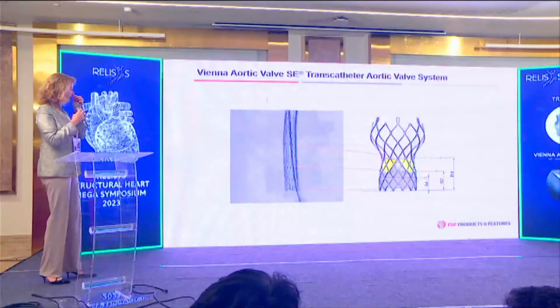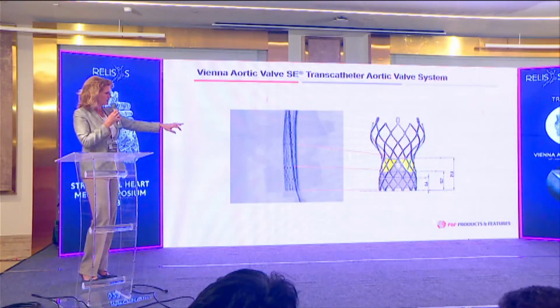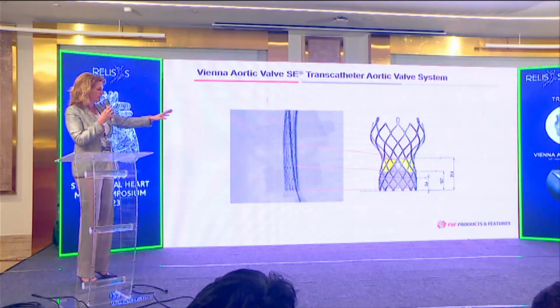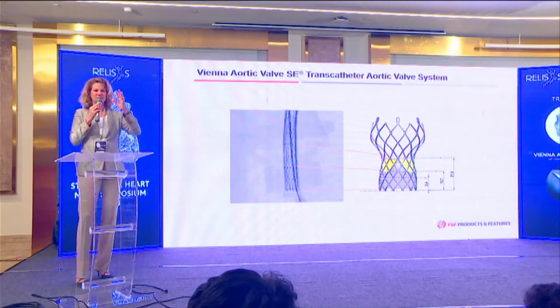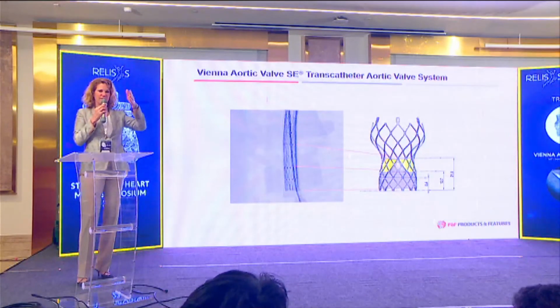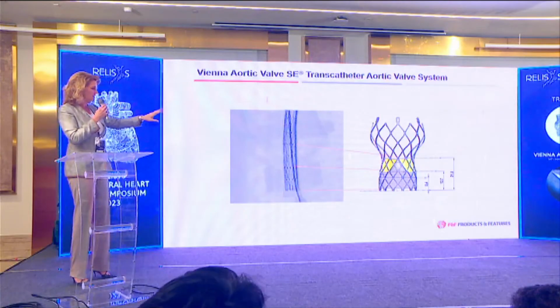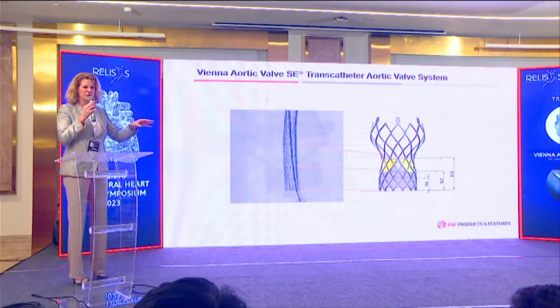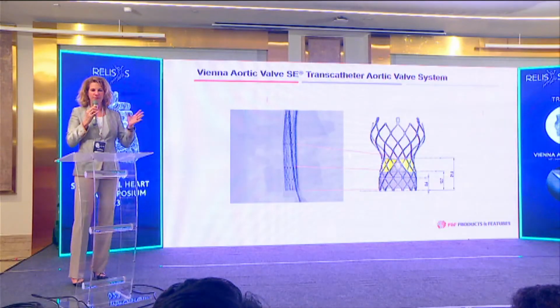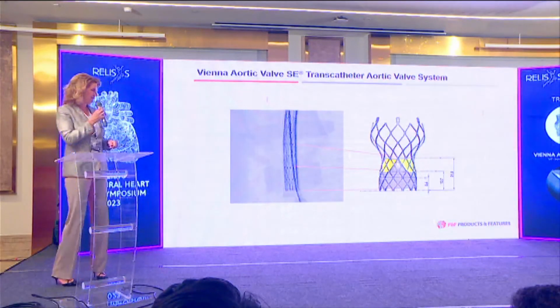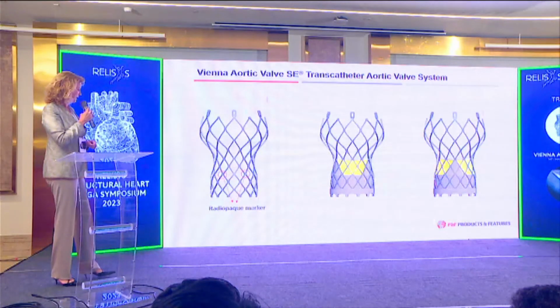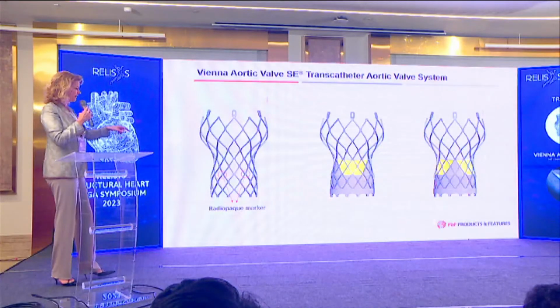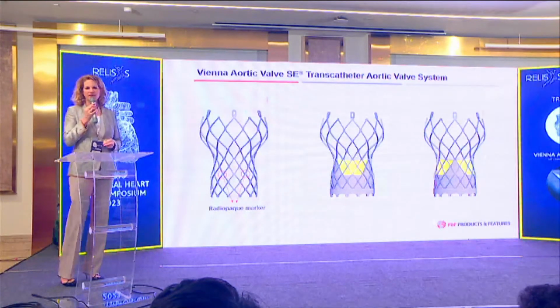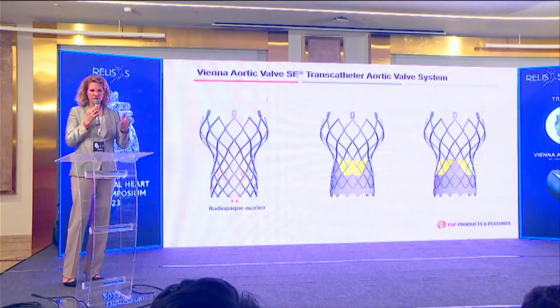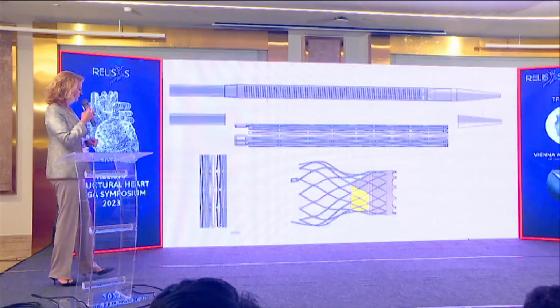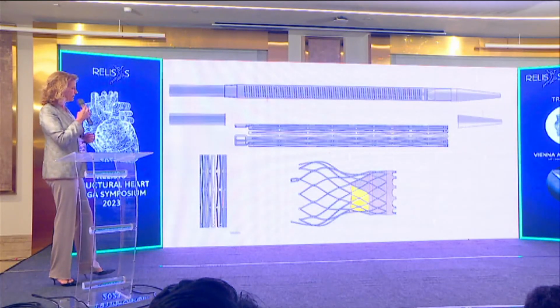Next slide, please. This we have seen, it's a very low skirt with 8.4 millimeters. If you remember the image of the Evolut, you can see that this has a much higher skirt, other leaflet geometry. So this has a low skirt with a very favorable leaflet geometry, which also has a good opening if you look at the leaflet geometry from above. Next. The next generation, as I mentioned, will have tantalum markers in order to facilitate your coronary alignment as well as your depth control. Next slide. And this is how the valve is crimped on the delivery device.